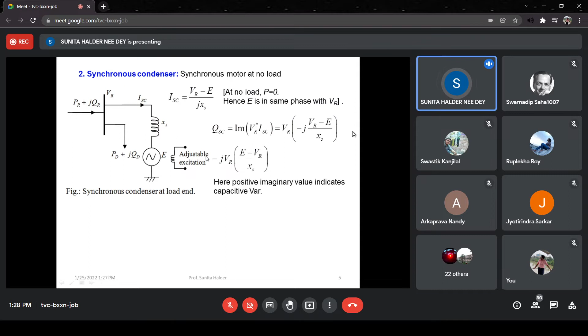Why voltage conjugate? Because current has a negative in algebraic form. That's why voltage conjugate. For algebraic form, we generally do not take the conjugate. So the positive imaginary part will give you the capacitive var, and the negative imaginary part will give you the inductive var. So when E is greater than VR, then this QSC will be positive. If we want to configure the synchronous condenser as a capacitor, then the excitation should be adjusted in such a way that E is more than VR.